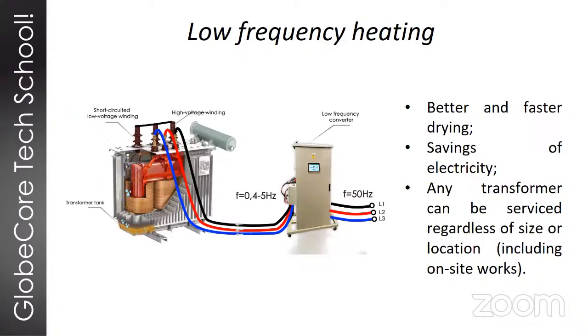In terms of real numbers, for a relatively small power transformer, that would mean about 2,000 kilowatt hours. When we use traditional methods of drying with circulating hot oil and vacuum for a large transformer, the average water extraction rate is about 2.5 liters per day. But when we have nozzle spraying of hot oil with low frequency heating, we get an extraction rate of up to 20 liters per day.